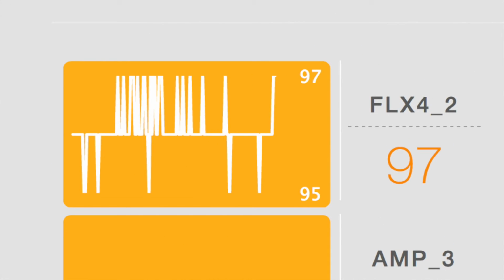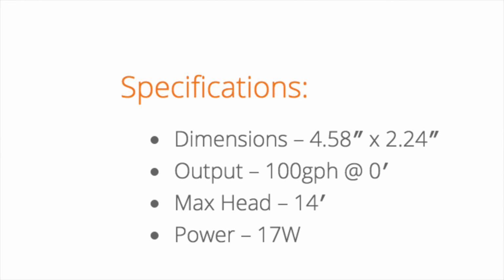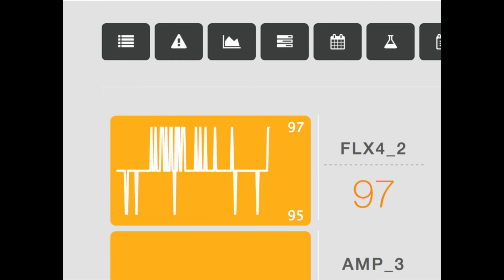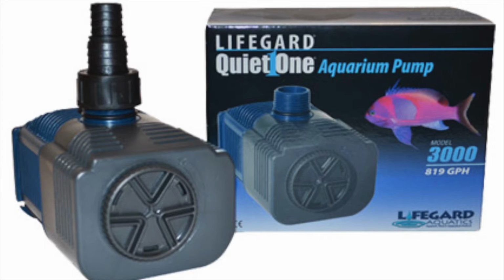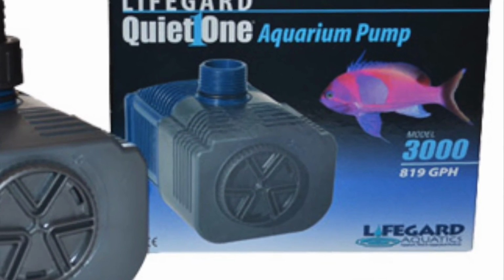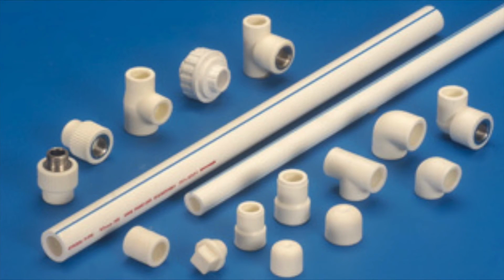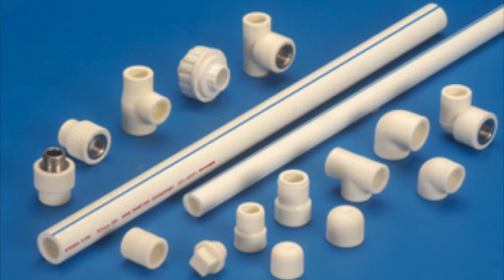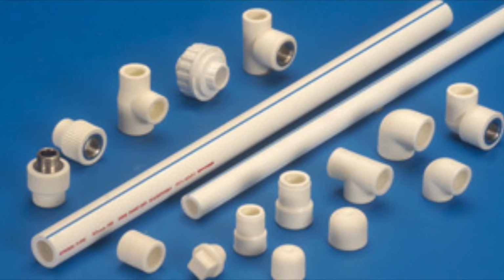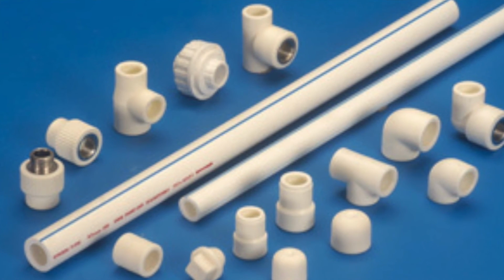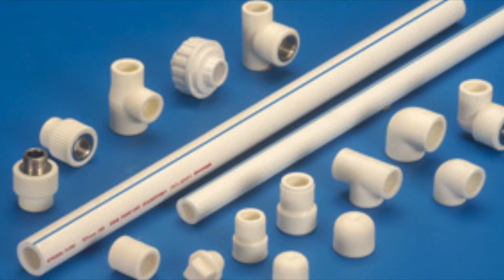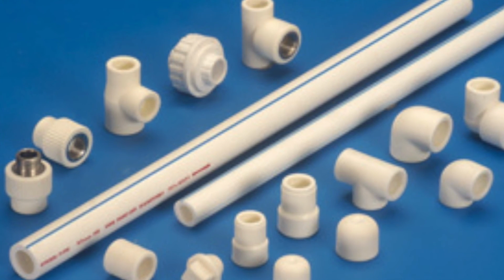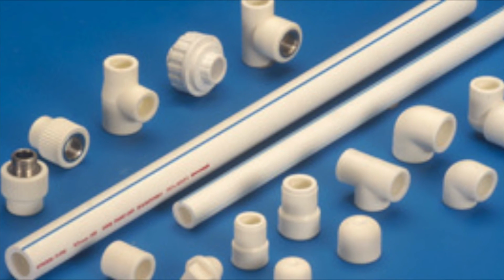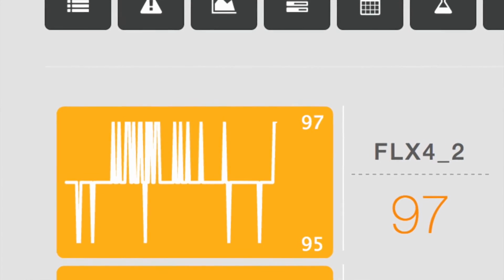Note, when you're looking at your flow sensor graph in Fusion, and you say in your head, I thought my pump was supposed to pump X amount of gallons per hour, and the flow graph is showing something different, why would this be? You need to remember that the gallon per hour number that a pump manufacturer gives on a product does not take into consideration pipe fittings like 90 degree and 45 degree angles, T's. All these things add up and cause reduction in the flow, just like the pipe length and vertical height all create head pressure and turbulence that will reduce the flow on the flow sensor. The key here is to look for trends.